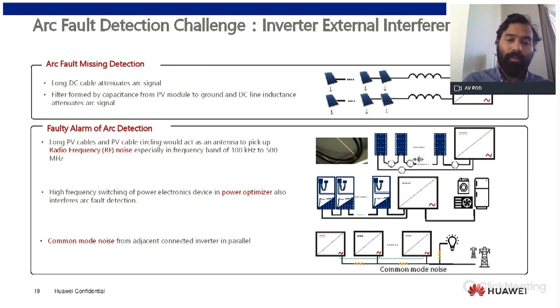Then you have the high frequency of extra components like optimizers. This will introduce some variation to the signal, and again could lead to a misleading or false arc fault event. And finally, the common mode noise between several inverters connected in parallel could bring again challenges to identify a correct arc fault situation. And these are the external factors.